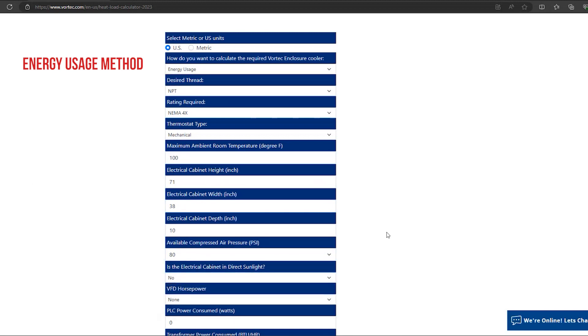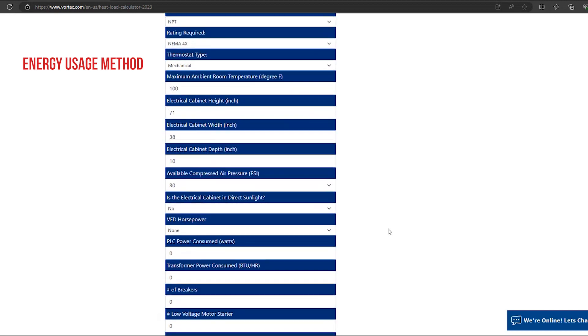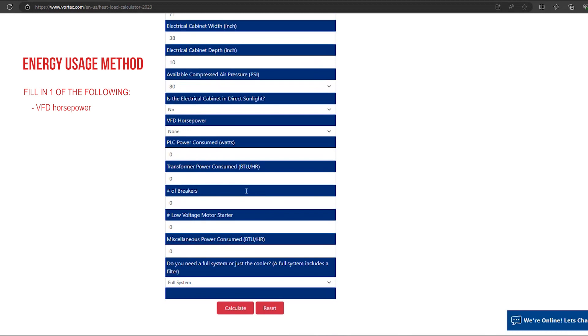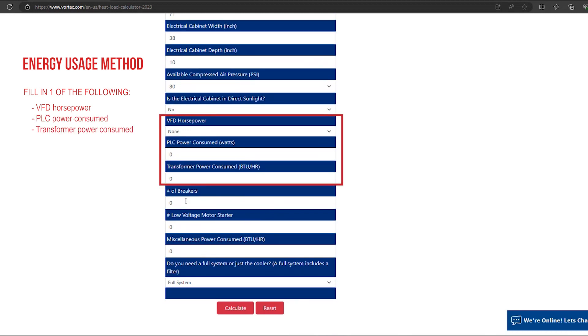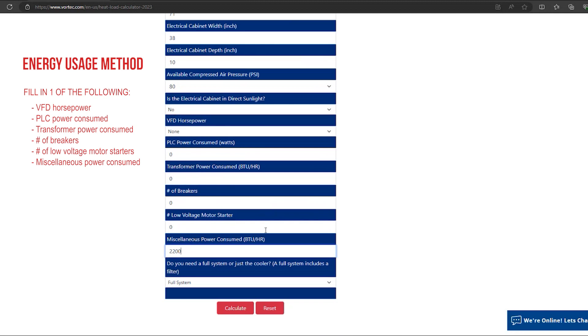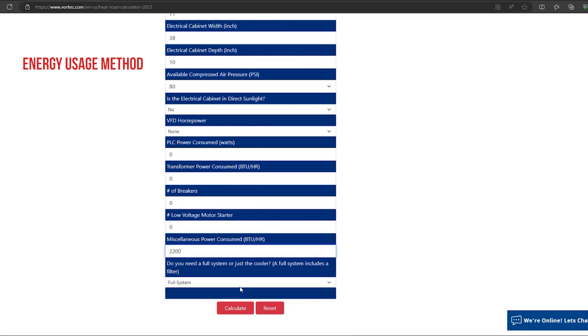After completing these questions, one of the following options must be specified: the VFD horsepower, the PLC power consumed, the transformer power consumed, the number of breakers, the number of low voltage motor starters, or the miscellaneous power consumed. If you know the total dissipated heat of the entire enclosure, then you should use the miscellaneous power consumed option.